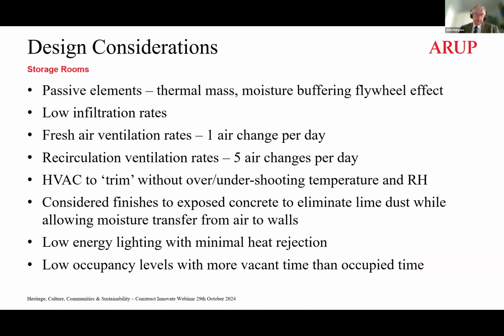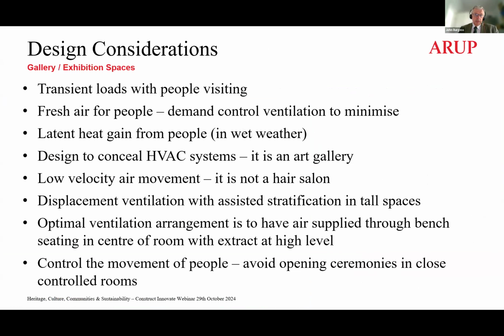So just wrapping up, some design considerations, apart from what I've just said. Low energy lighting, obviously, and low occupancy levels. And one's got to be careful that you don't mix up an archival storage area with that of a gallery where people are passing through. Remember about latent gain from people, particularly in wet weather. Try and have a cloakroom. Encourage people to take their coats and leave their brollies outside the gallery spaces.